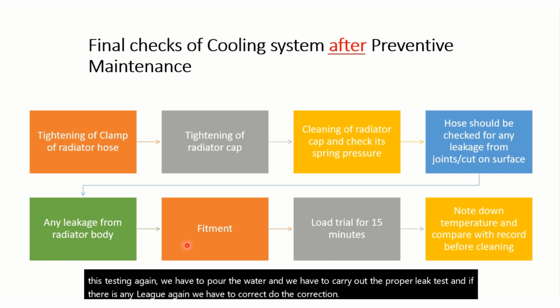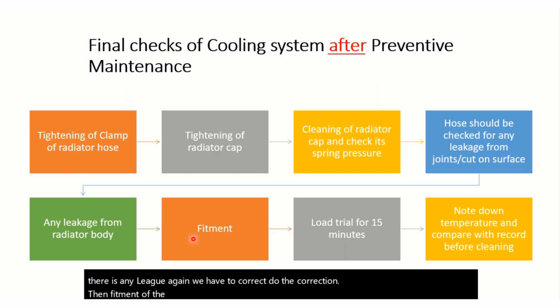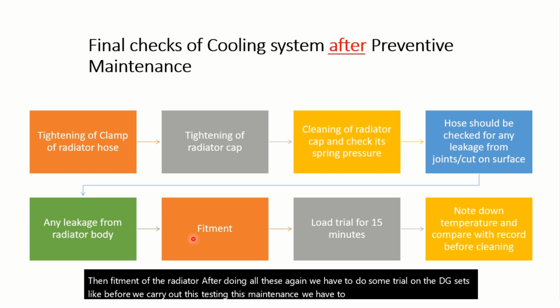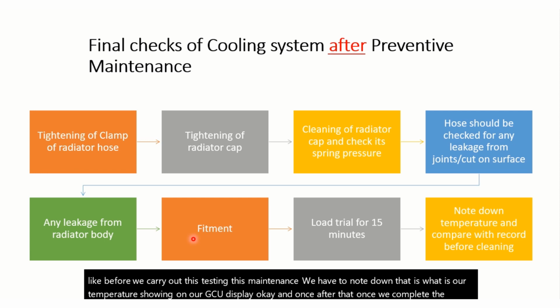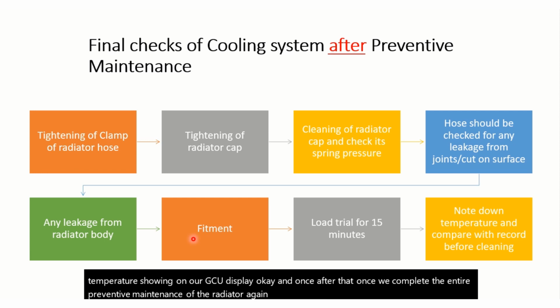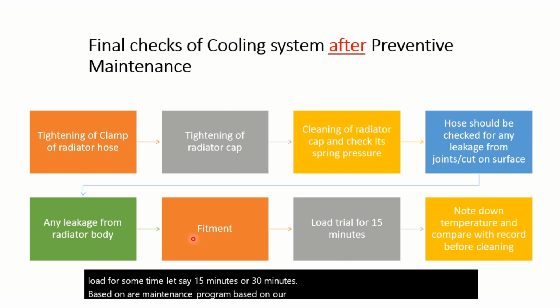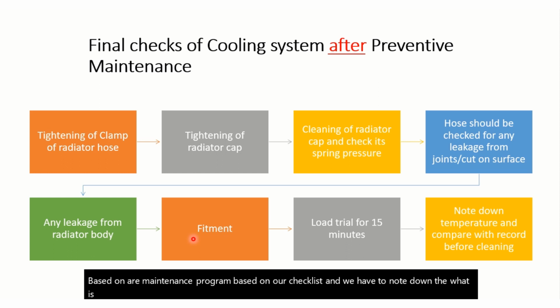Then comes the fitment of the radiator, and after all this we have to do a trial on the DG set. Before we carry out this maintenance, we have to note down the temperature showing on our GCU display. Once we complete the entire preventive maintenance of the radiator, we again take the diesel generator on load for some time, let's say 15 or 30 minutes, based on our maintenance program and checklist, and note down the maximum temperature it goes up to.